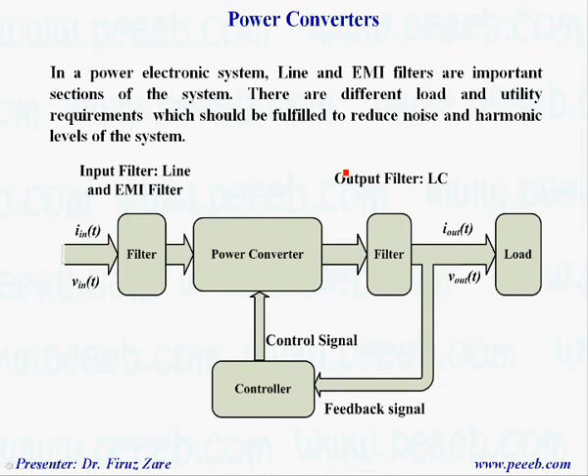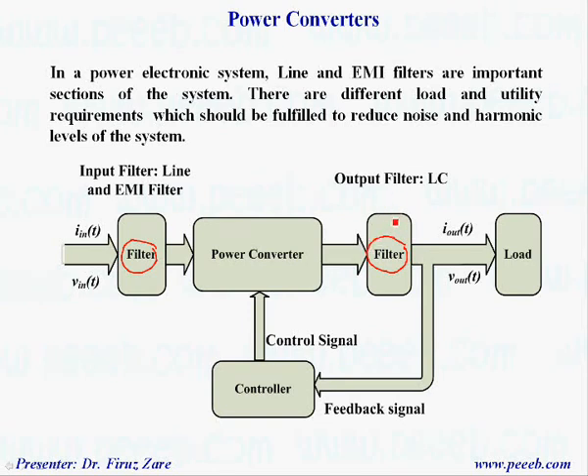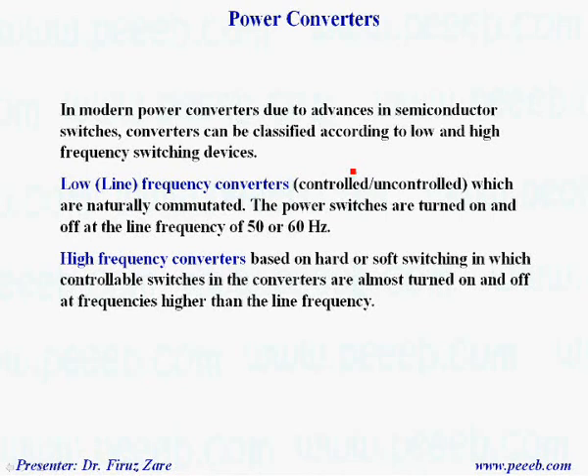In a power electronic system, line and EMI filters are important sections of the system. We need filters on the input side and also on the output side depending on the application. Sometimes we don't need an output filter, especially in AC motor drives, but for power system applications or UPS (uninterruptible power supply) we need an output filter. The input filter is also important because we should control low-frequency and high-frequency noise. In modern power converters, due to advances in semiconductor switches, converters can be classified according to low and high frequency switching devices.